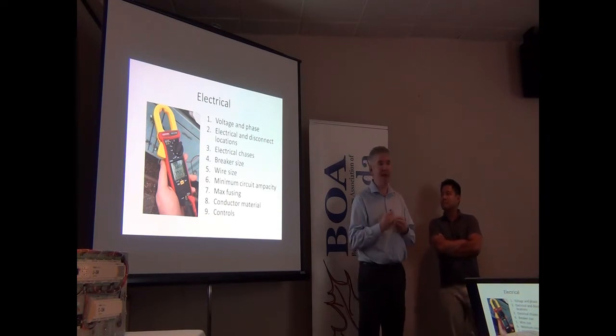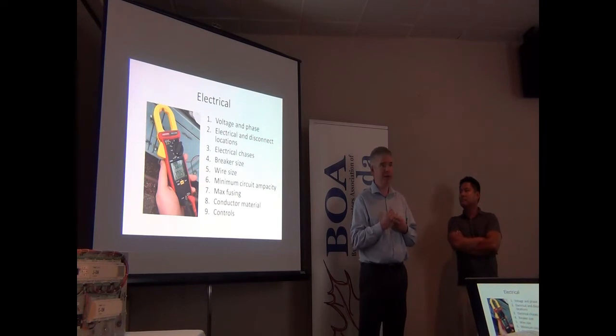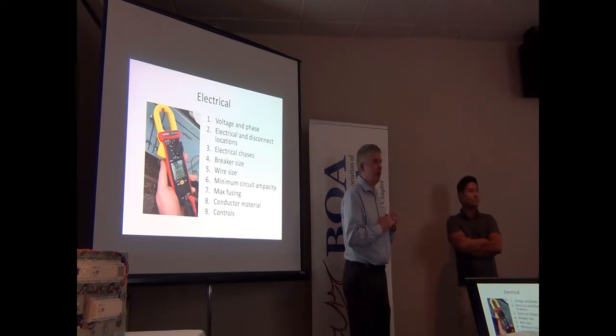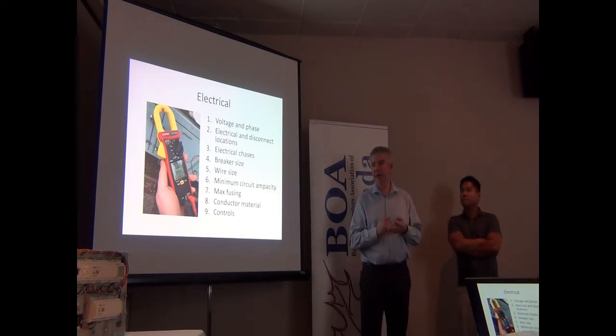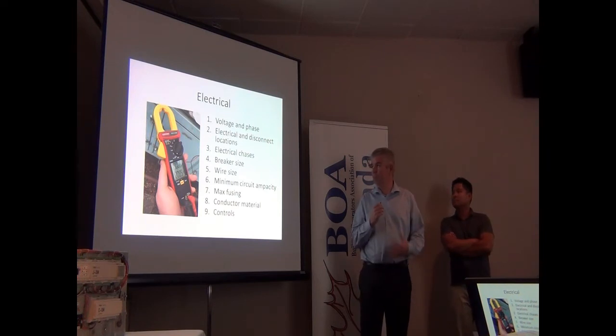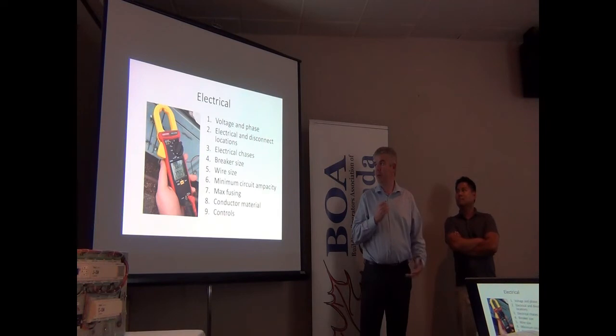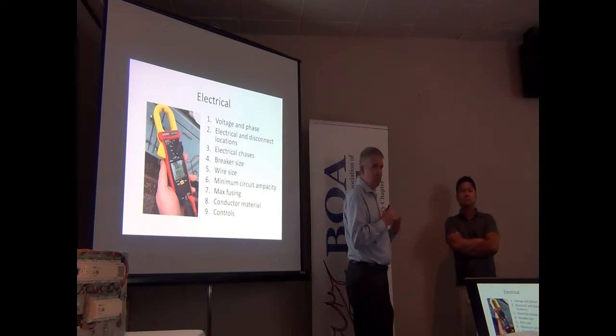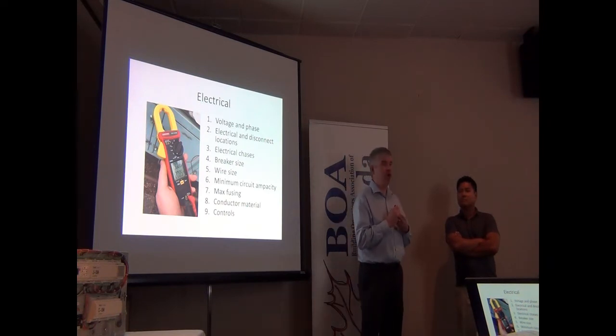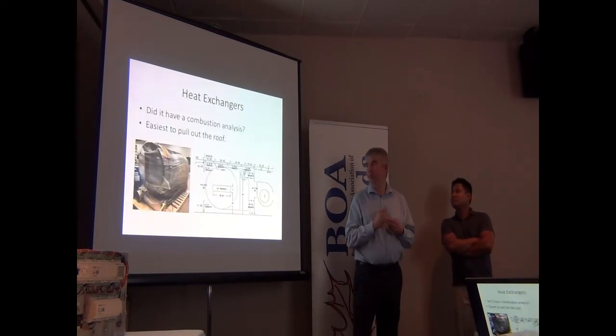Larger can also happen for the same thing, adding capacity. It's hotter out. You may have more of a heating load in the building that you need to cool in the summer. You may have more outdoor air that you need to cool and deal with. So now do you have the proper wiring there in the first place? Do you again have the proper size disconnects, proper service? Can your sub panels support what's actually providing to the unit in the first place? Those can be really big things to look at, but they're also very straightforward. If you know you're changing the application or you know you're changing the appliance, just be aware that you're going to have to look at it, and there could be substantial electrical changes. Also, it's possible that wire that was pulled and acceptable is no longer acceptable. Maybe you have aluminum conductors if it's an old enough building. Maybe you just have conductors that aren't sized adequately anymore for the conduits in which they're run. Also possibilities.